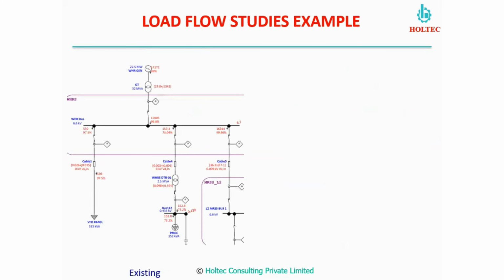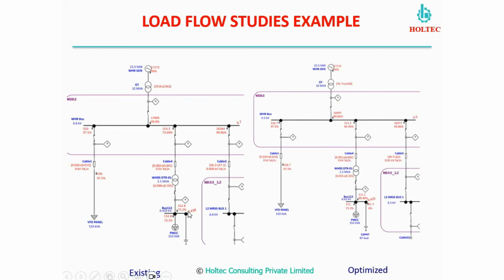This is another example where we have a generator, and here what is happening in the generator, we are maintaining 6.7 kV voltage, which is slightly on the higher side. Here also on LV we have 438 volt as against the 415 volt, which is our requirement. Okay, and last but not the least, the power factor on the LV bus is very poor. So when we do the corrective actions, we are able to maintain the power factor of this LV bus nearly unity by adding the capacitors, APFC, and also we have optimized the voltage.